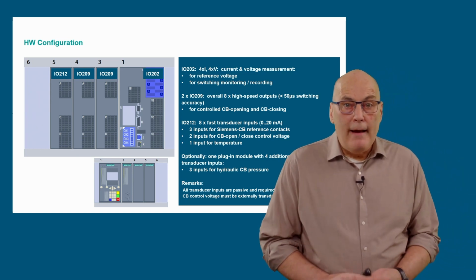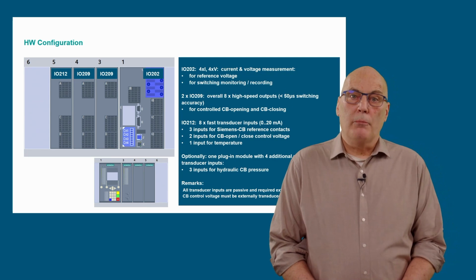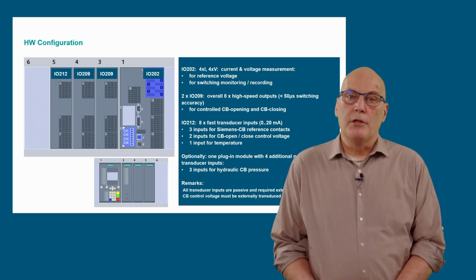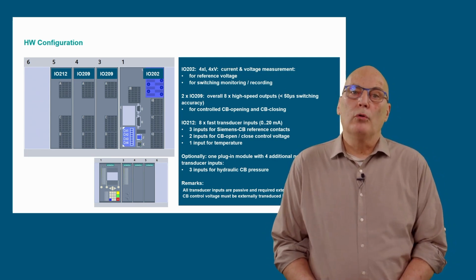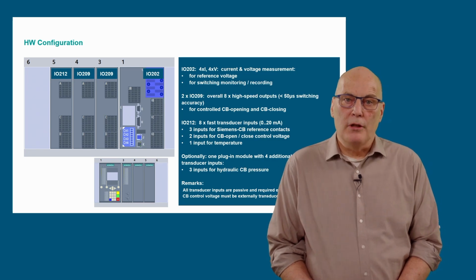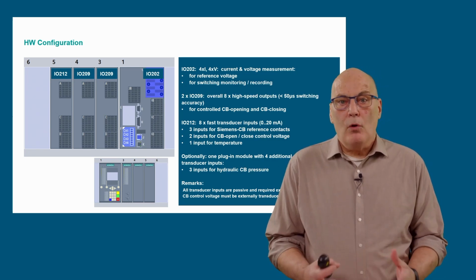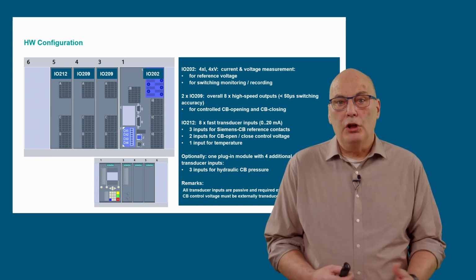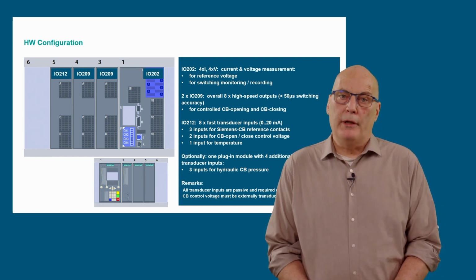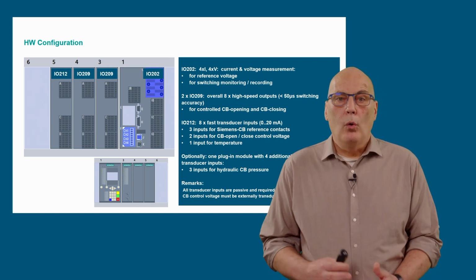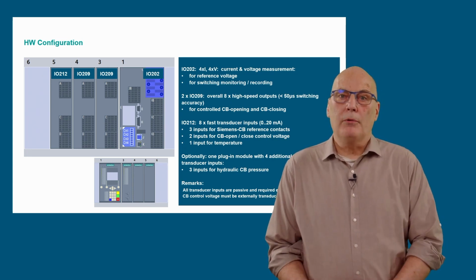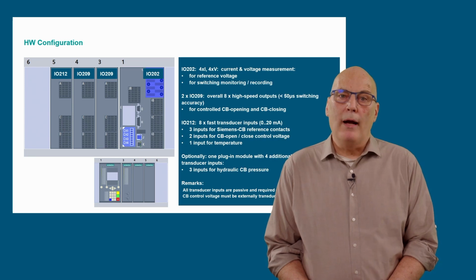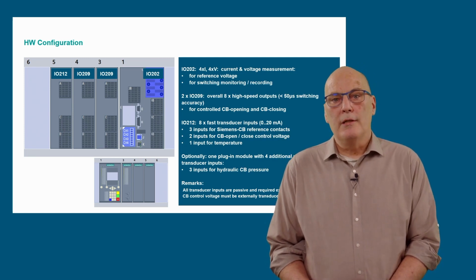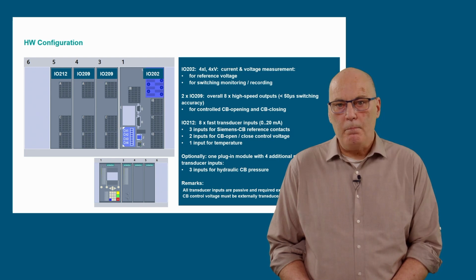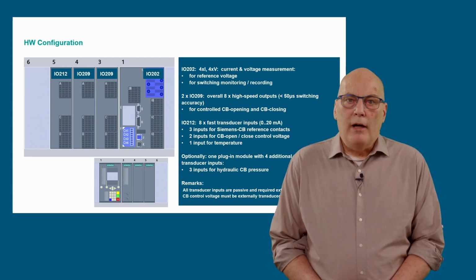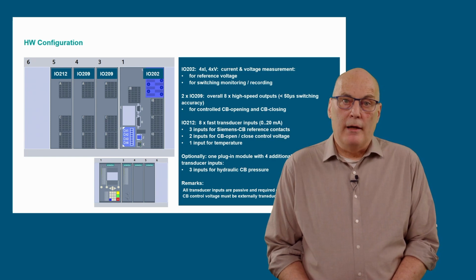Transducer inputs. If a reference contact is used in the circuit breaker, it must be connected to a transducer input on the IO212 module. Fast transducer inputs. The other optional inputs for temperature, voltage and hydraulic pressure may also be connected via the IO212. Alternatively, these not time-critical signals can be connected to a plug-in transducer card as shown in slot F. Other SIPROTEC 5 features may be selected as desired.